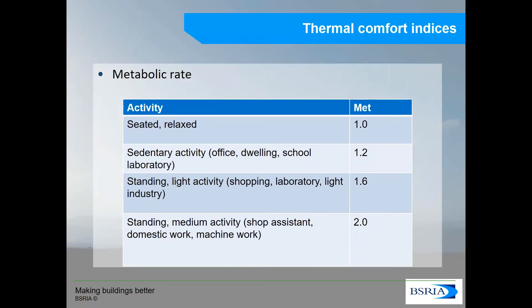The next thing to take into consideration before calculating the thermal comfort indices is the metabolic rate. The metabolic rate gives us an indication of the activity that we are carrying out, and as you can imagine a person will not feel the same in the same environment if they are sitting down or if they are running. In an office environment we would probably have a metabolic rate of 1.0 or 1.2, which is equivalent to a sedentary activity. But for example in a hospital environment we could have a higher metabolic rate.